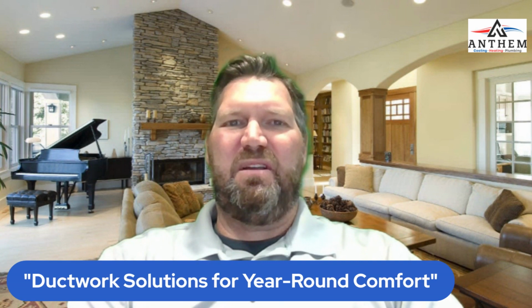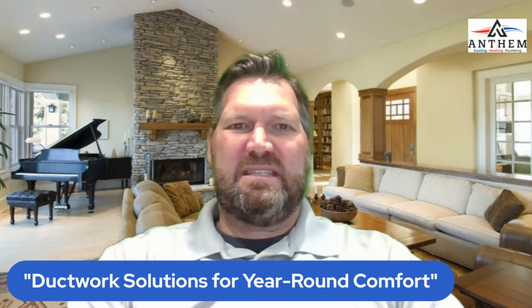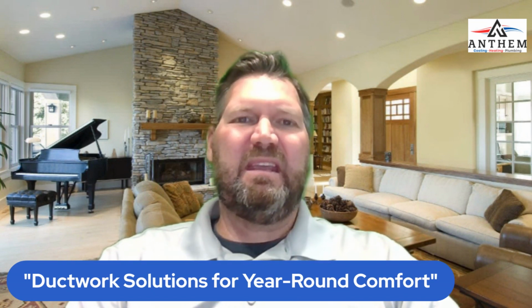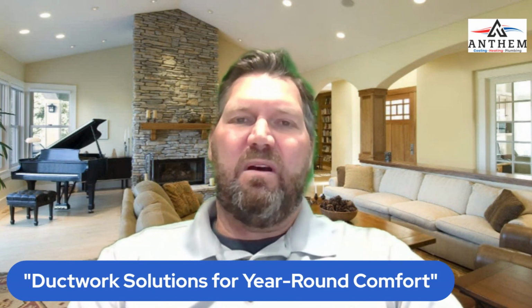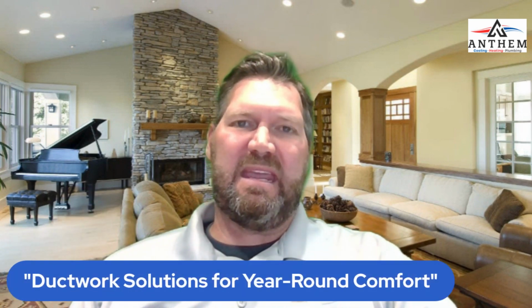All right, sounds good. So today's topic is ductwork, and ductwork is the most inefficient part of an air conditioner system. In previous topics, we talked about equipment efficiency, and we went into SEER ratings. Well, when we do SEER ratings for ductless systems, our SEER can get all the way up to like SEER 30, SEER 40. I mean, they go really high in the ductless systems. But the SEER ratings in ducted systems tend to be somewhere around 14. You're topping out somewhere around 20, 22. And that's mostly because of the inefficiency that the ducts cause in a system.